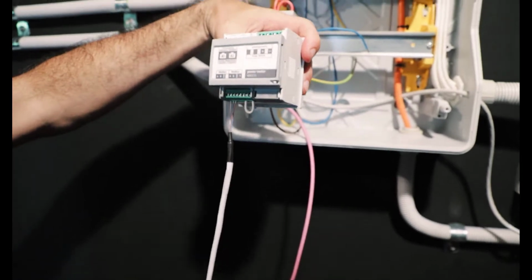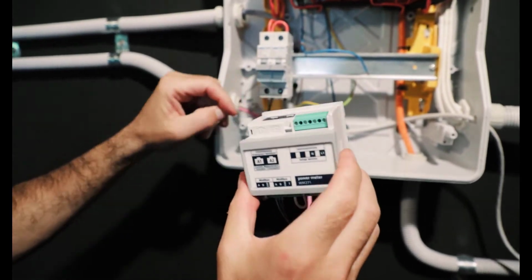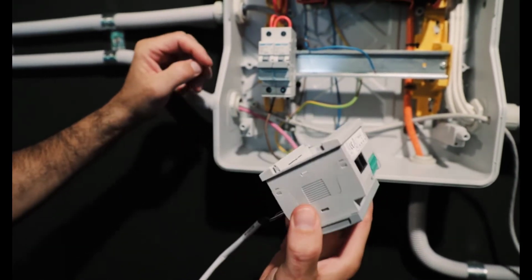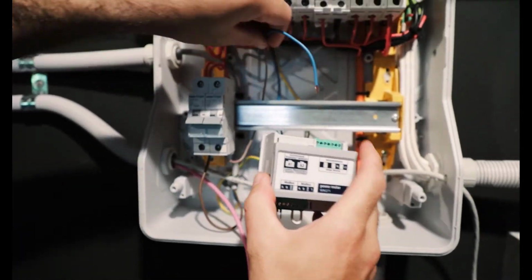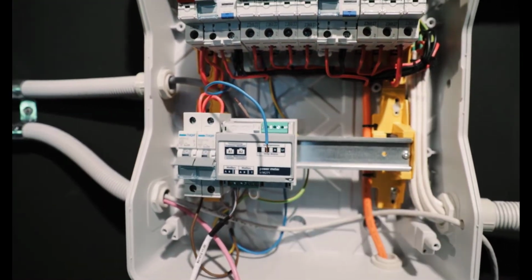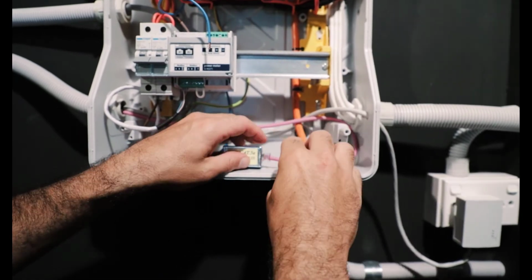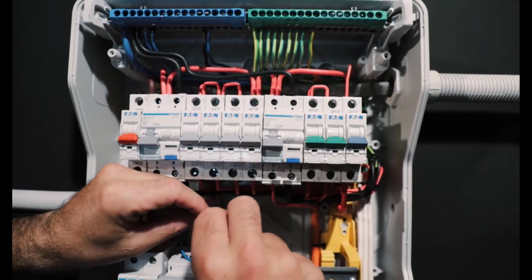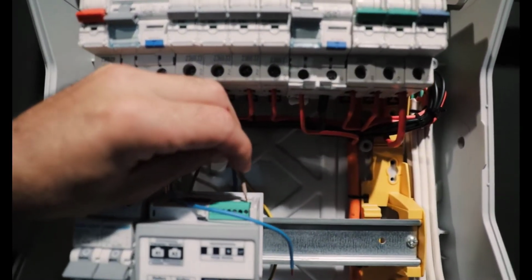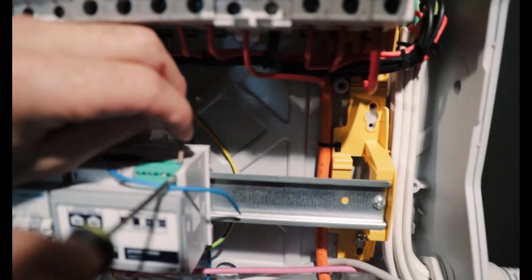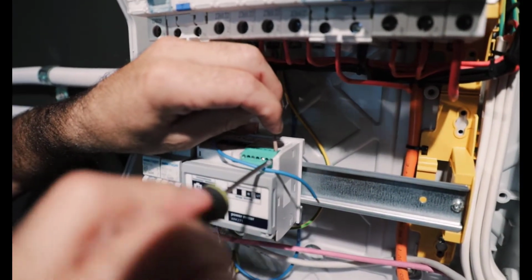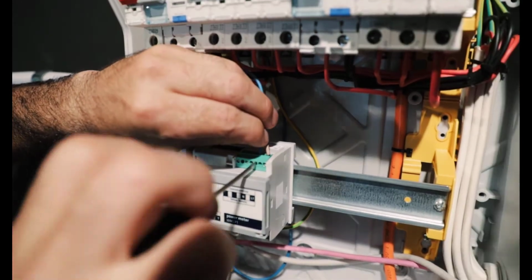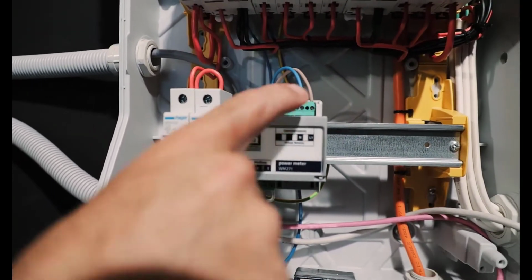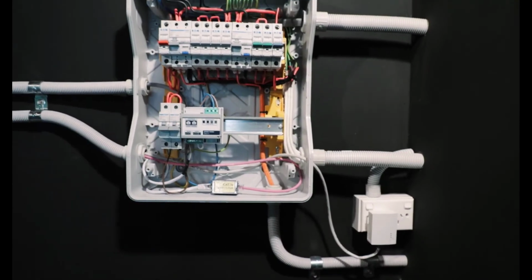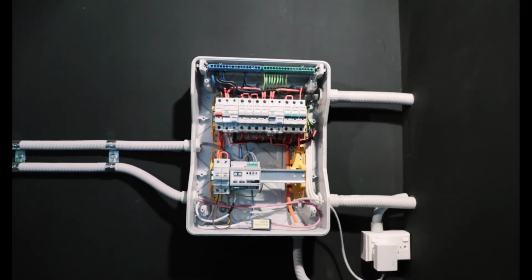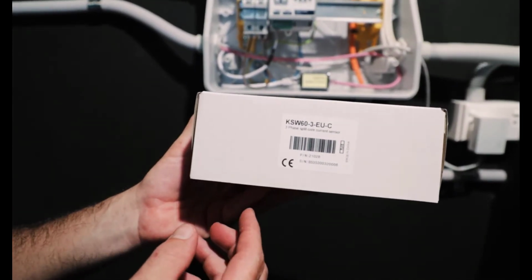Now that little jumper tells us that this meter has already been pre-wired and pre-programmed to be able to allow for the grid consumption. Previous sonnen systems you had to program them, but this one's already been pre-programmed. So active goes in, and then neutral goes in. Okay, and as you can see here on the single phase systems, it's very clearly labelled where neutral and active need to go. So here we're now going to bring in the CT sets.